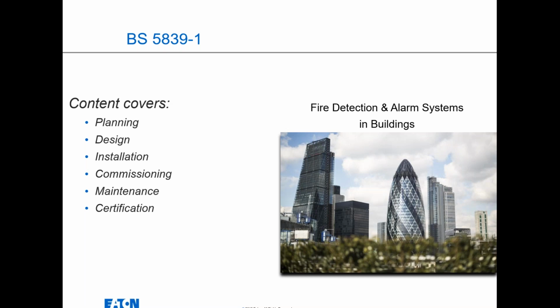I know a lot of things that don't happen, so no design certification is issued at that stage. Install certificates sometimes don't get done, and certainly commissioning certificates sometimes can get missed. But without those, you're really leaving yourself open to the fact that the system is non-compliant. So if anything did happen, and obviously remember it's a life safety system, then you could be liable. And obviously with Grenfell, we know that somebody's probably going to end up facing some prison charges when the case comes to court.